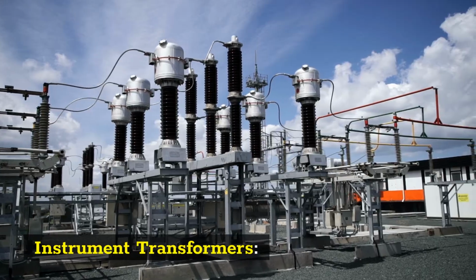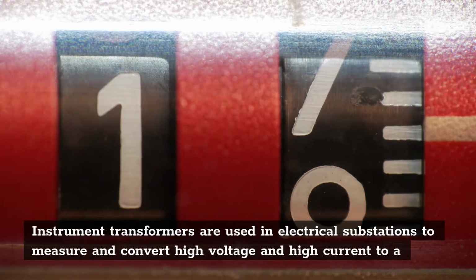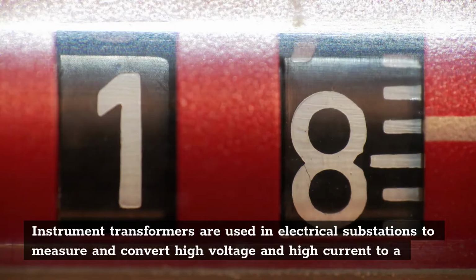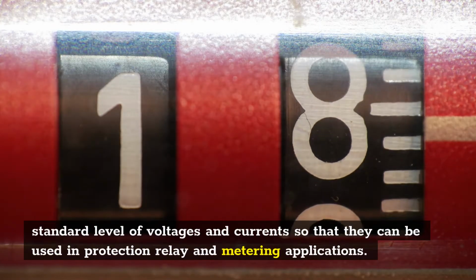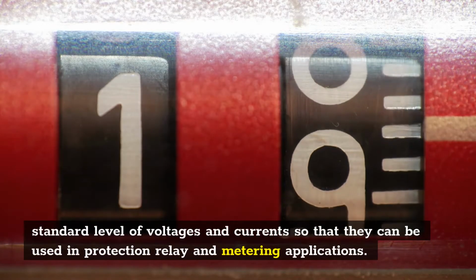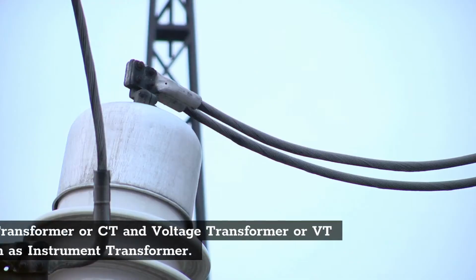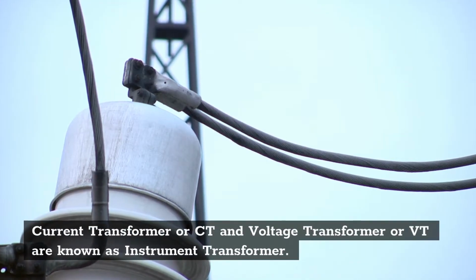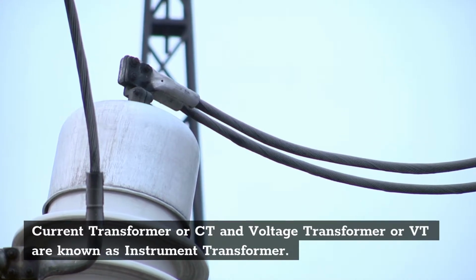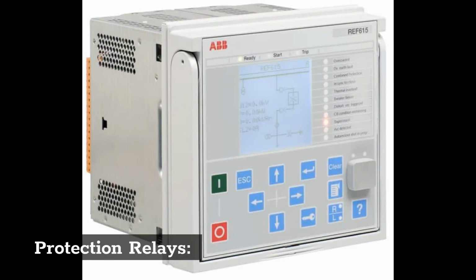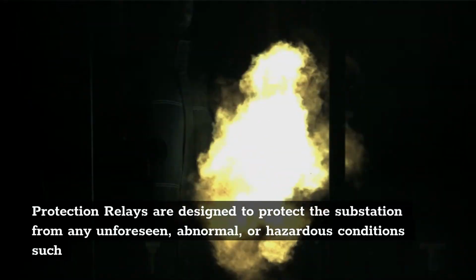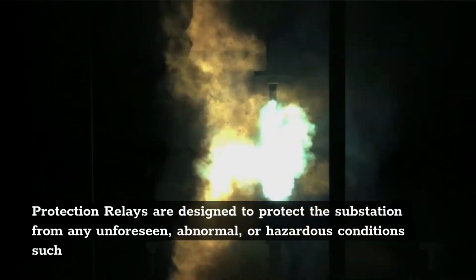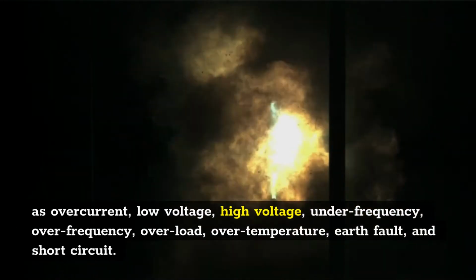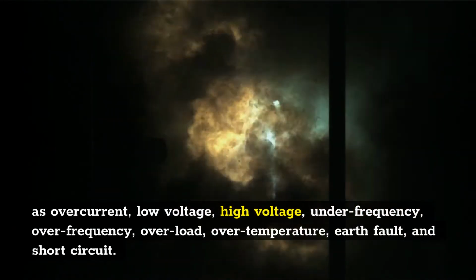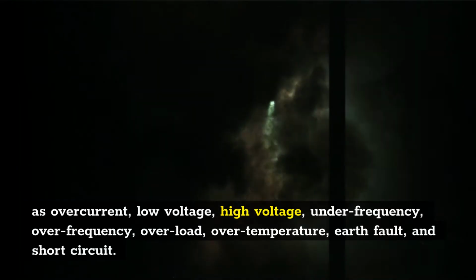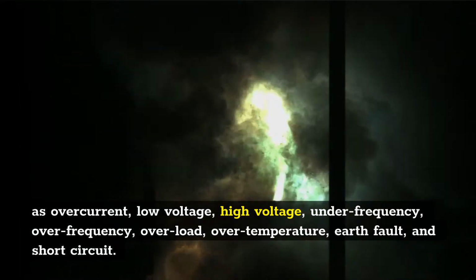Instrument transformers. Instrument transformers are used in electrical substations to measure and convert high voltage and high current to a standard level of voltages and currents so that they can be used in protection relay and metering applications. Current transformer or CT and voltage transformer or VT are known as instrument transformers. Protection relays. Protection relays are designed to protect the substation from any unforeseen, abnormal, or hazardous conditions such as overcurrent, low voltage, high voltage, under frequency, over frequency, overload, over temperature, earth fault, and short circuit.